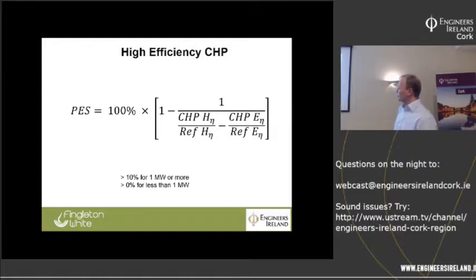And how do you calculate the primary energy savings? Well, you've got the CHP heating efficiency, which is the heat output from the CHP divided by the fuel input, and that's useful heat output. I have to introduce the concept of useful heat because it's very important. Useful heat is defined in the directive as an economically justified heat load. So one that you would have provided heat for without the CHP.